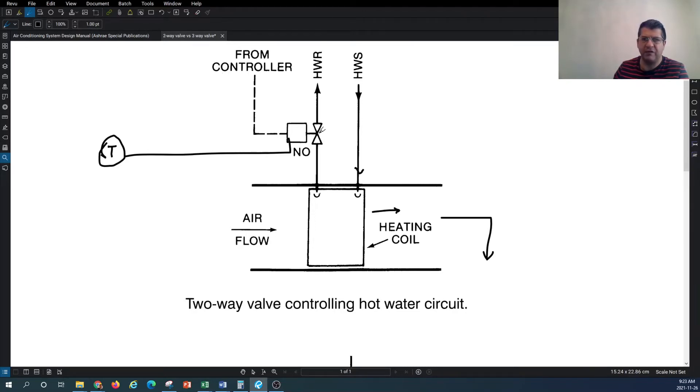We have talked about this in previous tutorials many times—the relationship between flow, pressure drop across a valve, as well as the CV of a valve, which is the constant coefficient provided by the manufacturer. You can create higher pressure drop across the valve and get lower flow passing through. You have to look into your valve, size it, and make sure you select the proper type of valve for this control.